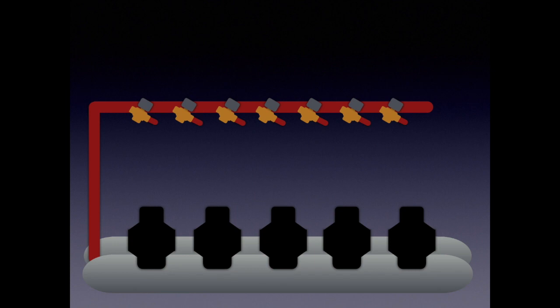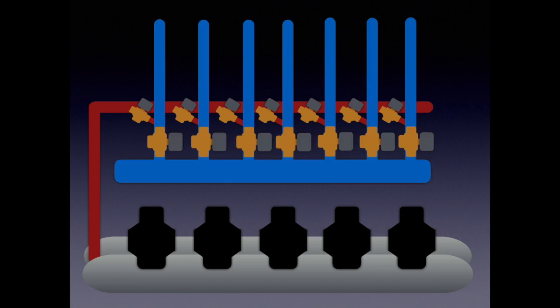And what we're doing here is we're taking hot vapor off the top of the receiver. And we're dumping it straight into the suction line. Just above those EPR valves. So that when we go into defrost, our defrost solenoids open and our EPR solenoids close.